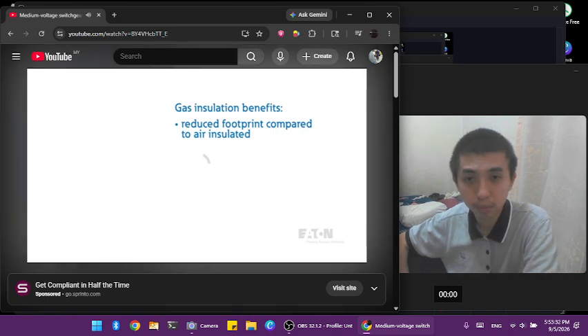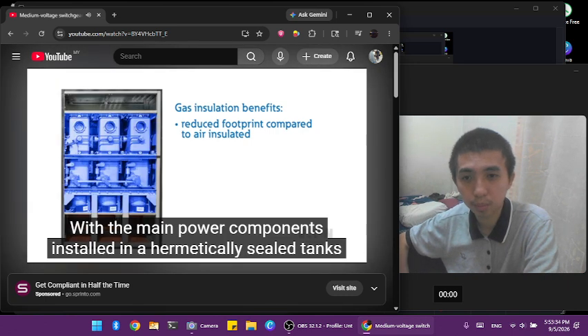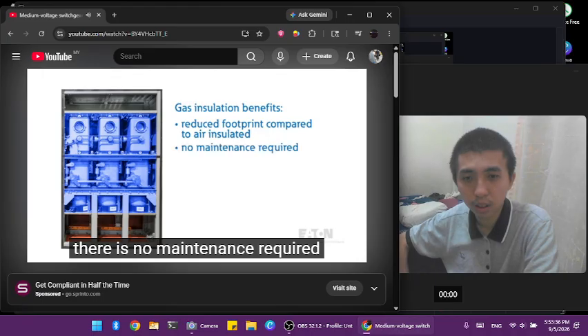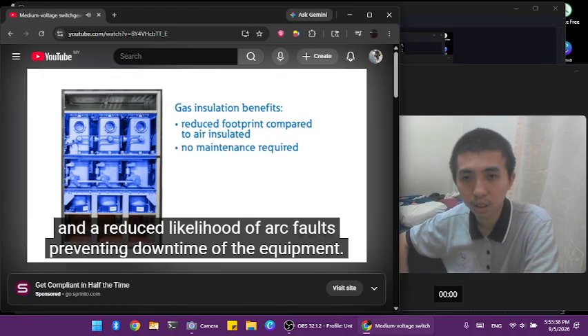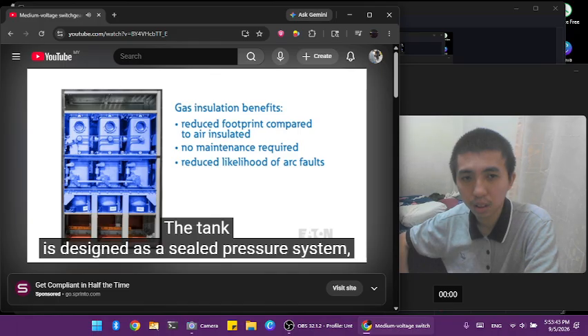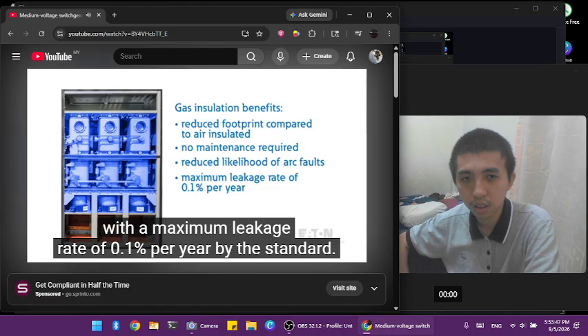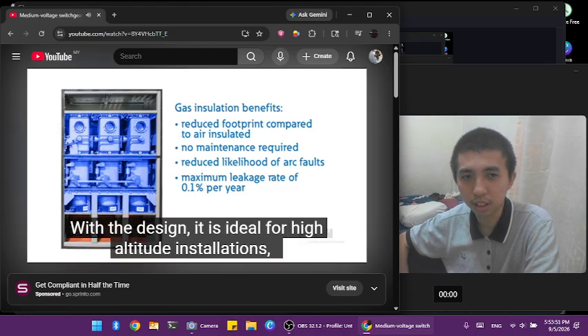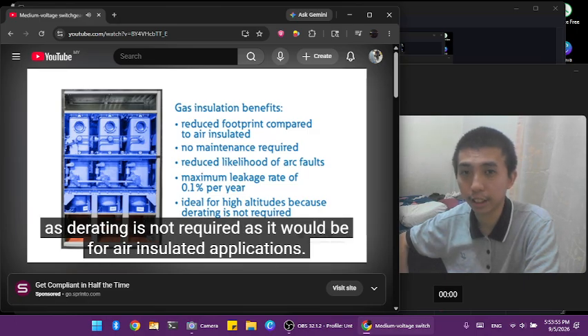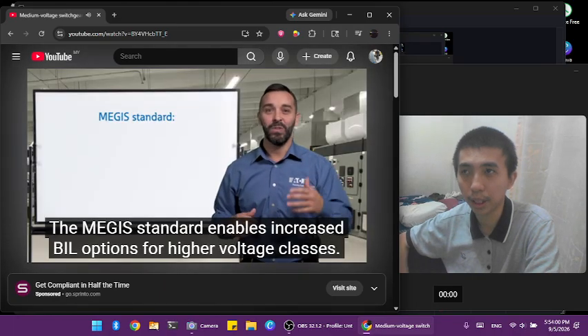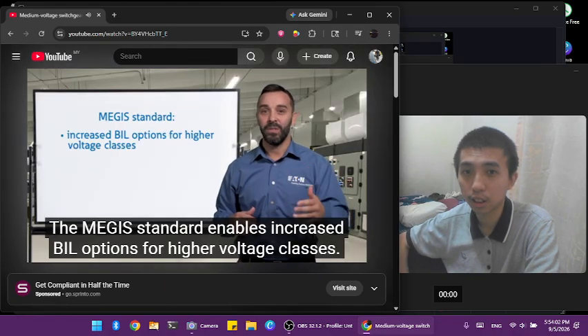With the main power components installed in hermetically sealed tanks, there is no maintenance required and a reduced likelihood of arc faults, preventing downtime of the equipment. The tank is designed as a sealed pressure system with a maximum leakage rate of 0.1% per year by the standard. With the design, it is ideal for high altitude installations, as derating is not required as it would be for air insulated applications. The MEGIS standard enables increased BIL options for higher voltage classes.